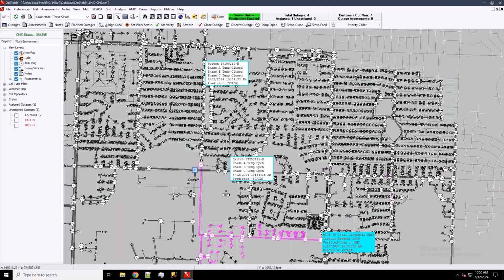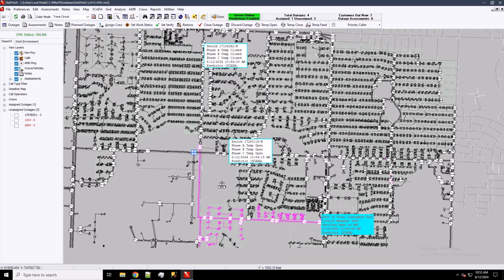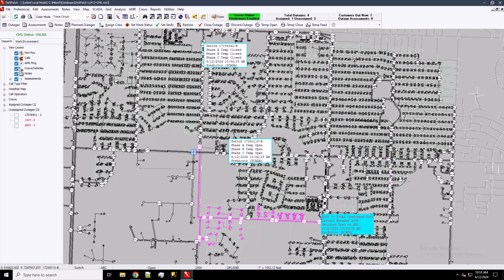I spent 8.5 years at a utility myself, and sometimes these temporary backfeed scenarios become less temporary over time. We might backfeed an area, and the normal open point kind of moves to a different spot. So we want to close out this demonstration by restoring this breaker and getting the remaining 5 customers on.